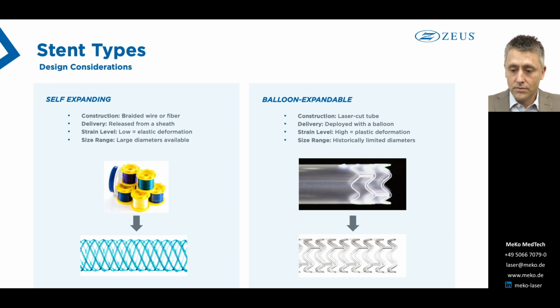Also, one very important difference, as we'll discuss later in the talk, is the strain level that the stent experiences when it's delivered. So for a braided stent, it's a very low strain level, which stays in the elastic region, and it gives that nice elastic pop out of the sheath. Whereas for a balloon expandable stent, the strain level is high because you have very localized strains. And that provides a plastic deformation, which, as we'll get into later, is by design.